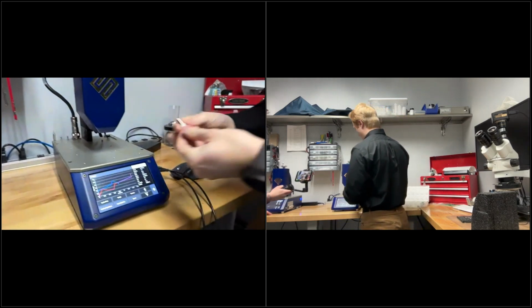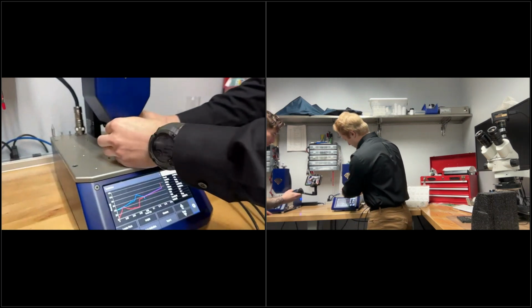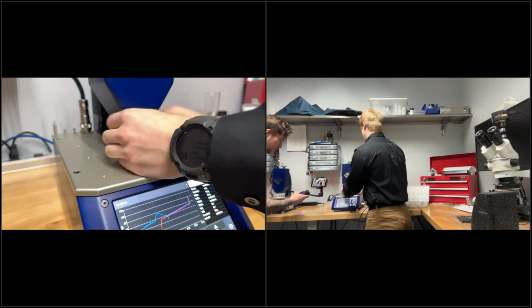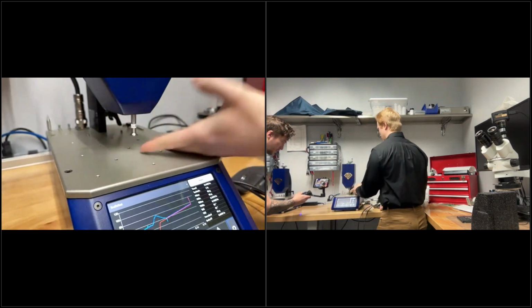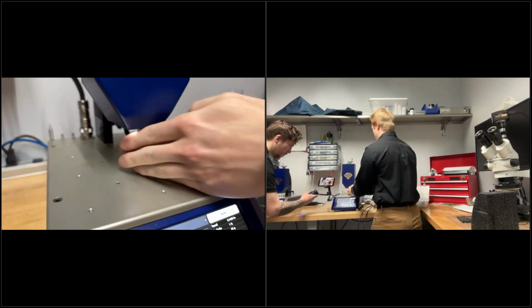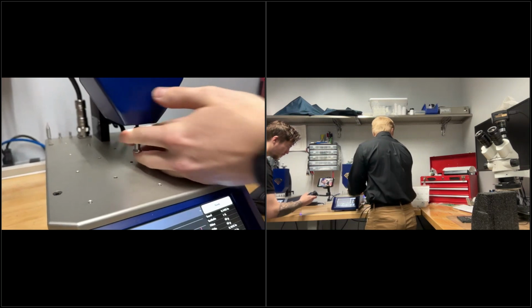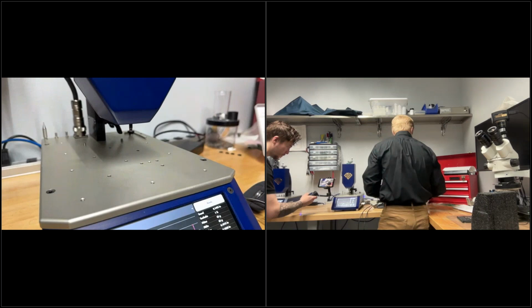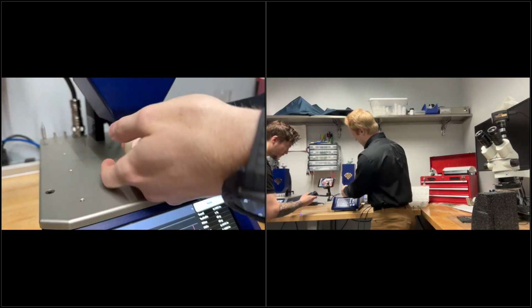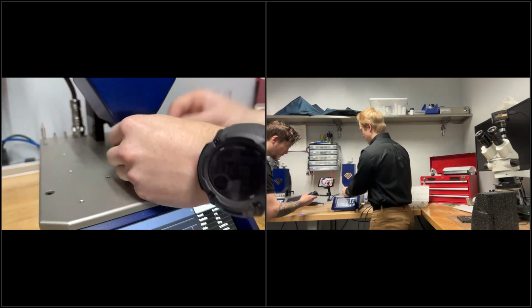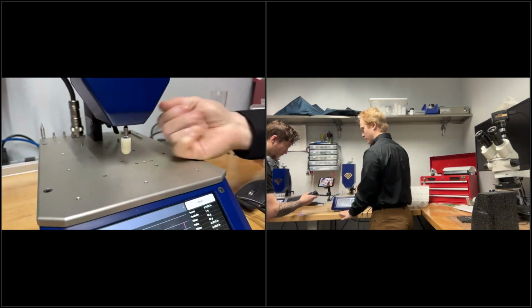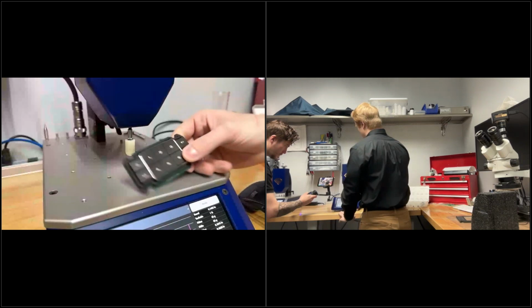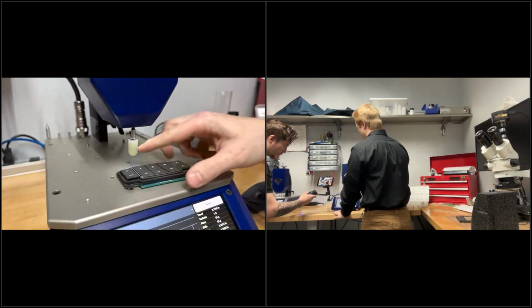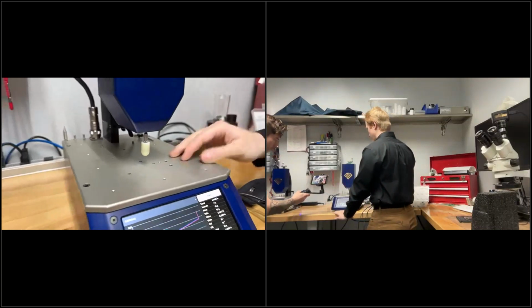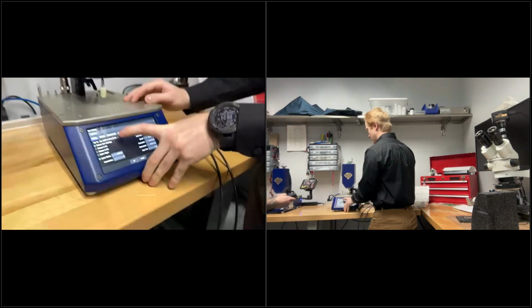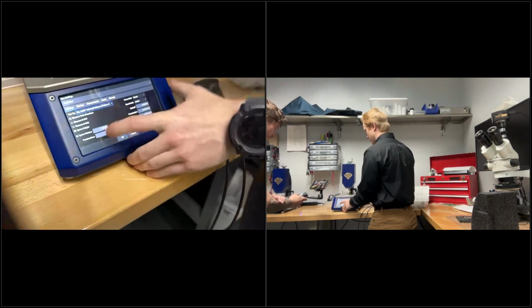such as this 1/2-inch flat plunger here. All I have to do is put it on the end of the test probe, thread it on, and then that's how you change your test probe. Another one that we have that's really interesting is our 5/8-inch rounded silicone tip, and what this is useful for is simulating essentially what the end of a human finger would interact with your assembly. So if you are testing a full product such as this and you want to know what that would look like characteristically with a human fingertip, that's a good option as well. And then from there, you just have to go into test configurations and select the test tip that you are using. Just like that.